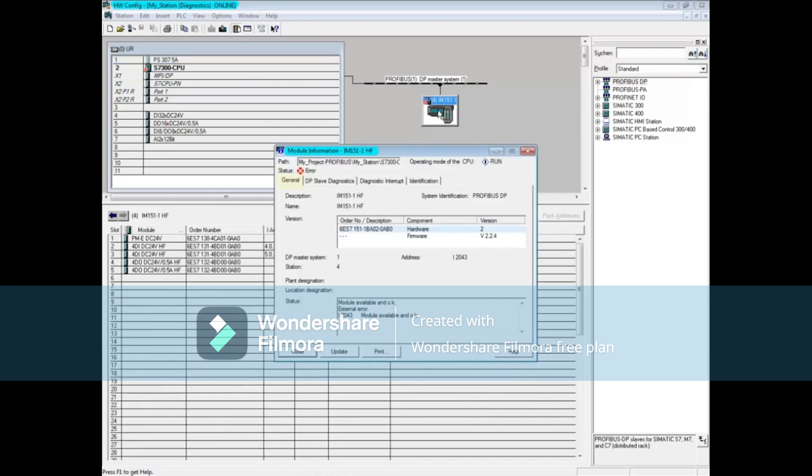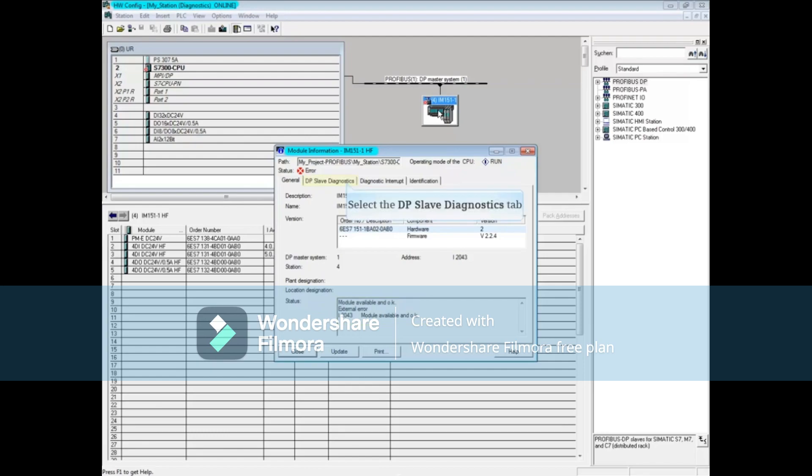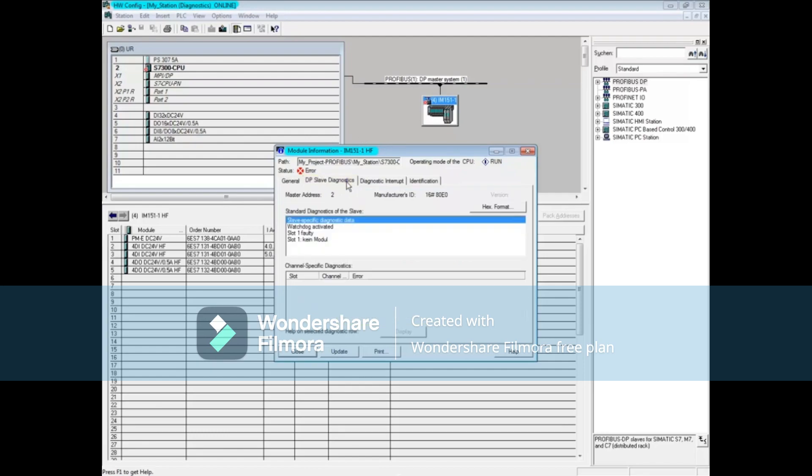The general tab says that the IM151-1 module is OK, but there is an external error. Let's click on the DP slave diagnostics tab. Here you see that slot 1, which contains the power module, is faulty.